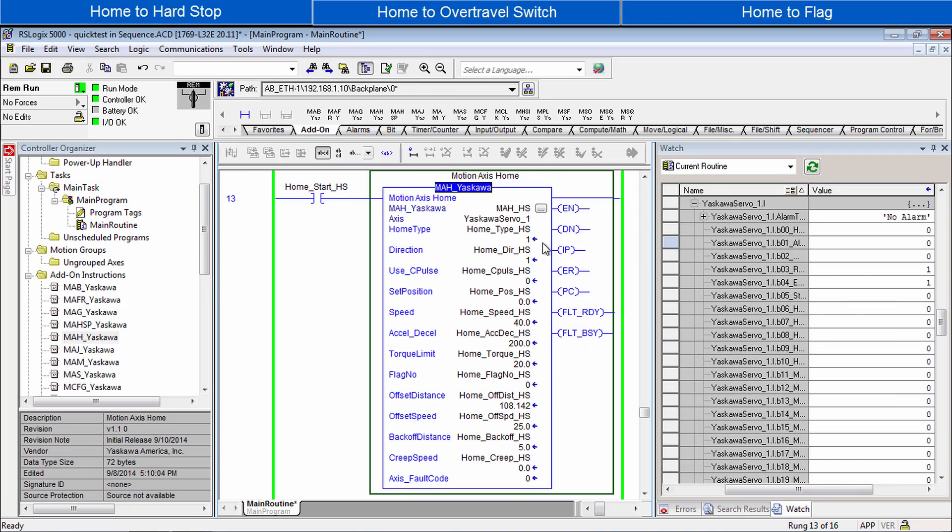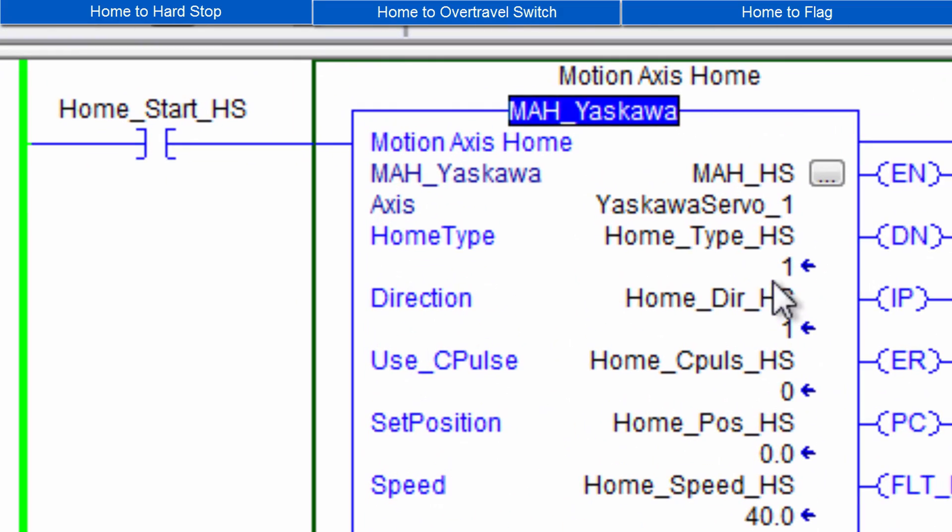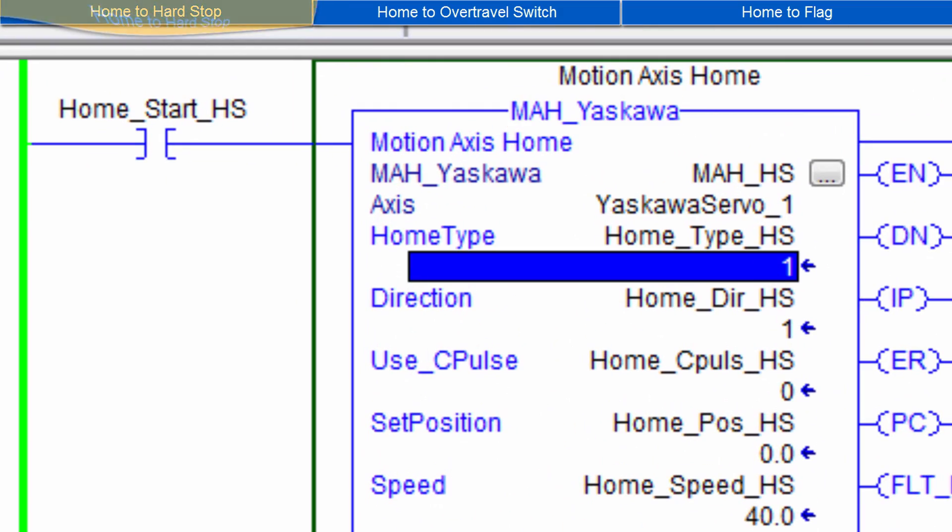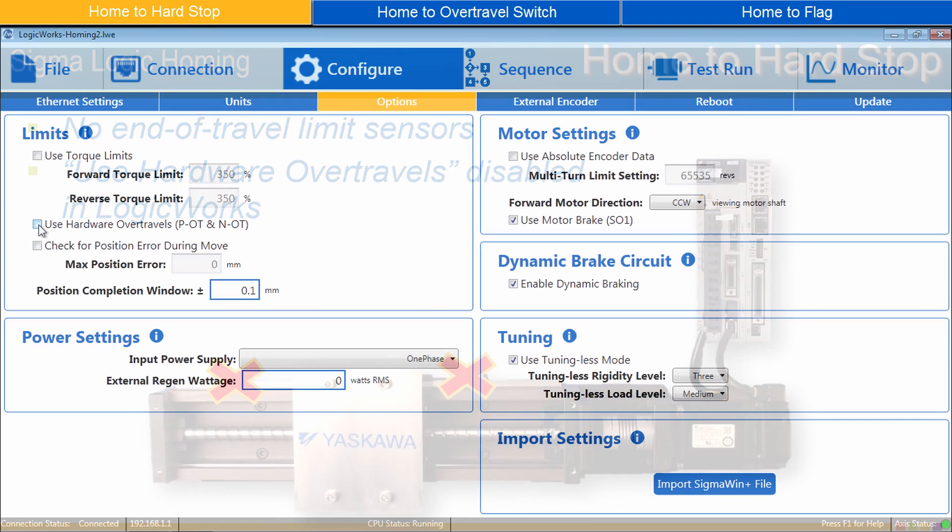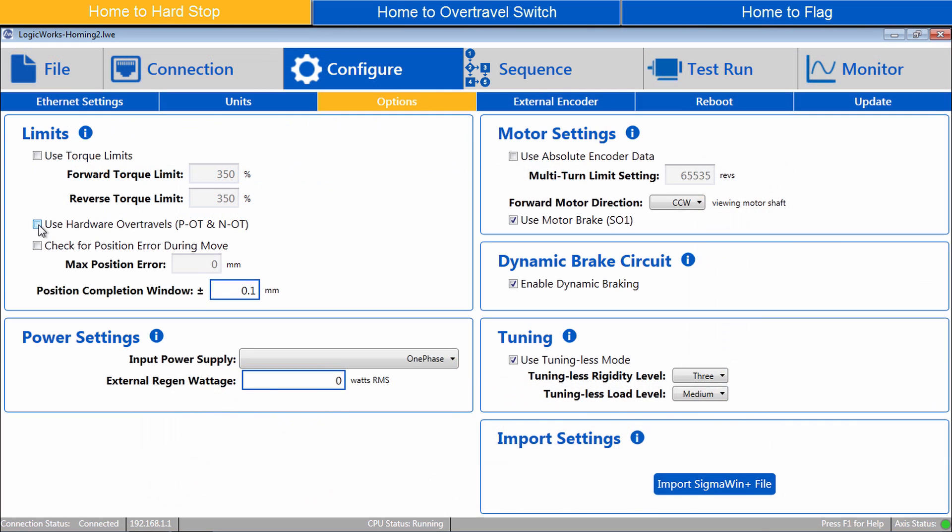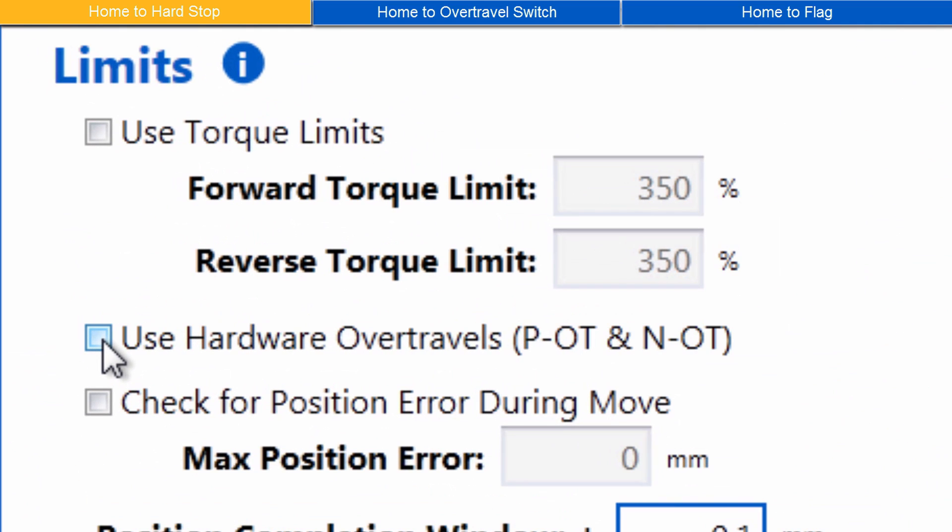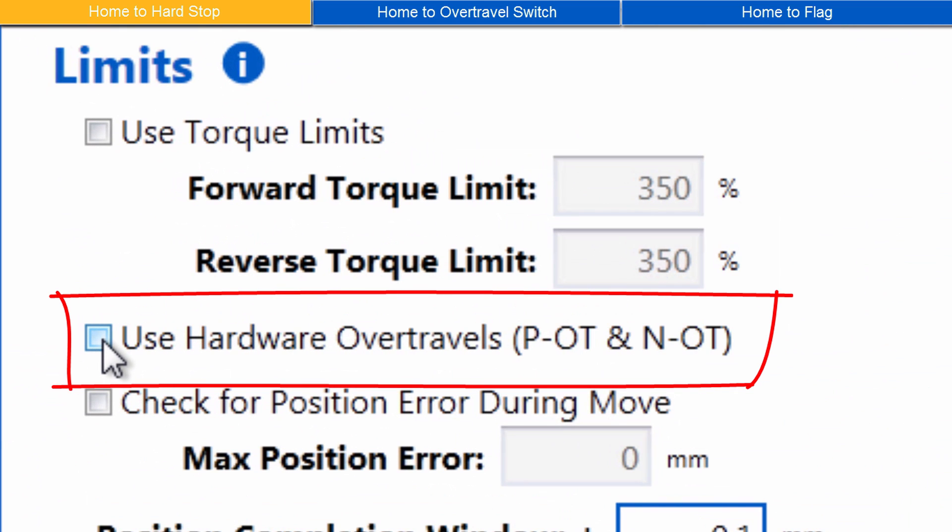Home to Hard Stop is Home Type 1. Hard Stop Homing applies to linear mechanisms without end-of-travel limit sensors. This means the over-travel function of the Sigma logic is disabled.